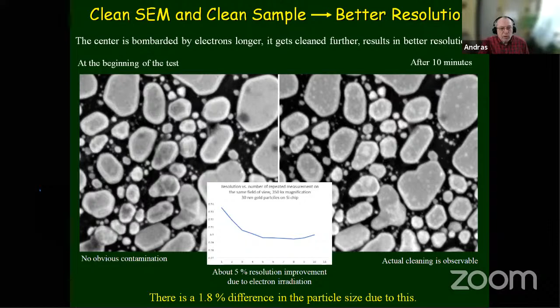you evaluate the so-called resolution with this software, FEI Image or Thermo Fisher Image, that I showed earlier. Then take another image and another image, and you get improvement in resolution, about 5% further improvement, because the electron irradiation removes very tiny amounts of leftover material. So you end up with a cleaner surface. Why is this important? Because there's about 1.8% difference in particle size measurements due to this. So if you measure at the beginning and measure later after the electron irradiation of the sample, you will measure them smaller. Obviously, that's closer to reality. Next slide, please.